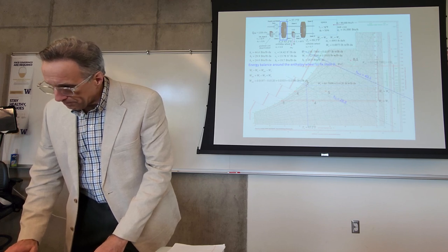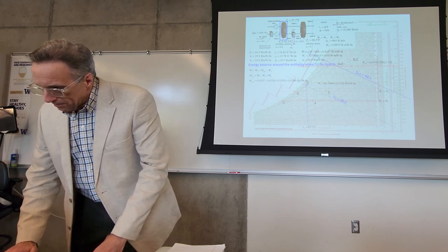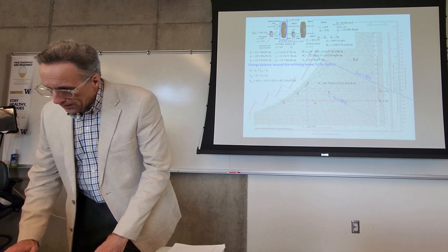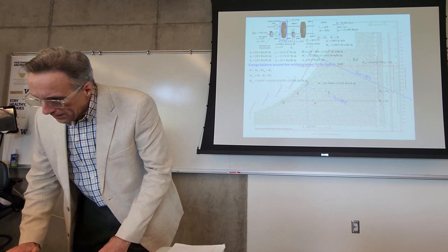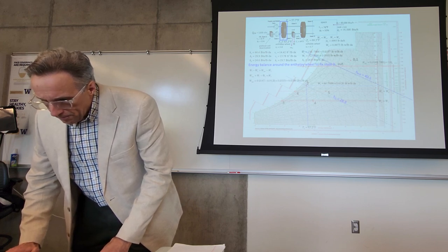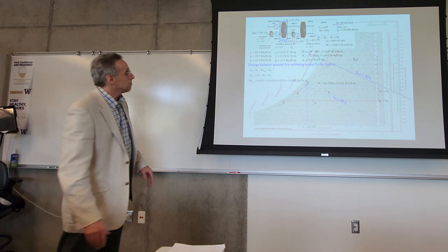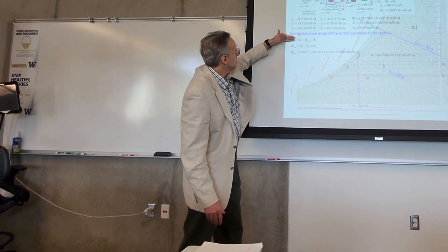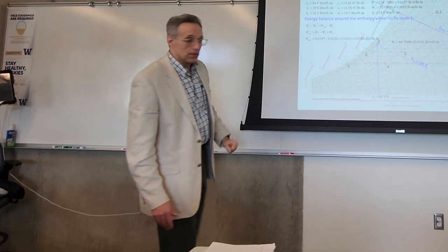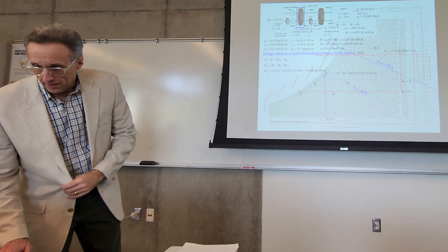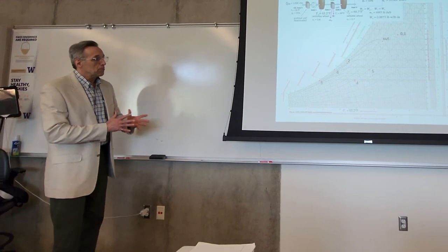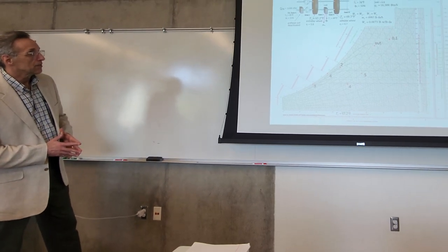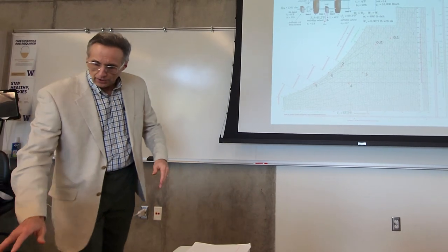And then the moisture at 0.0180. And this is from our moisture balance around the enthalpy wheel. It allows us to calculate the moisture coming out. And we've now located all of our points, our thermodynamic property points for each place in the system here. And now we can look at what's going on.